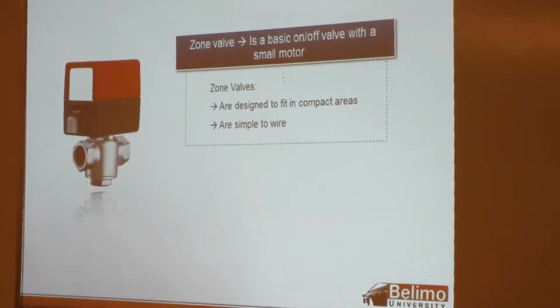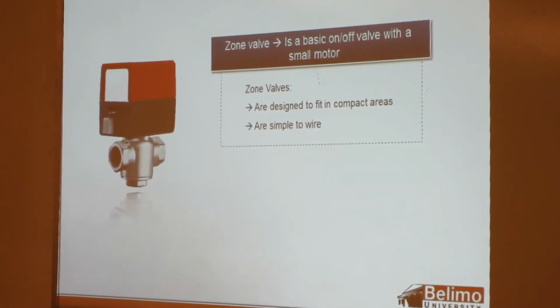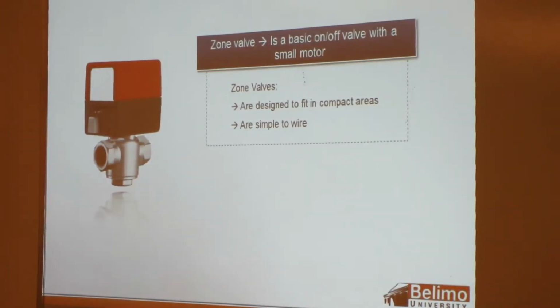Operation, like I said, it's a basic 2-position valve, small motor, spring return, designed to fit in compact areas. One thing I will mention, if you order a normally closed valve and really need it normally open, you just switch the actuator, because the actuator is what's deciding whether it's normally open or normally closed. There's no switches or anything on there that'll allow you to switch back and forth. So you want to make sure you get it right the first time.